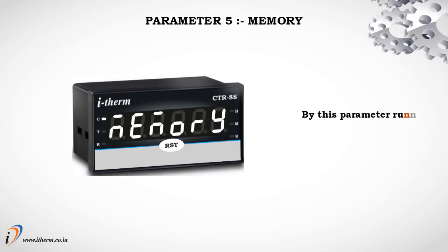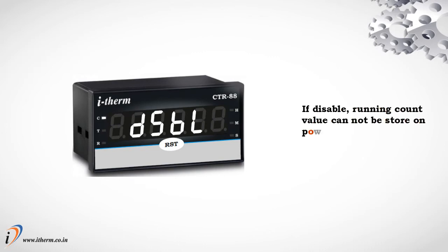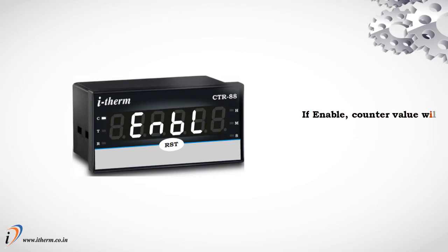Parameter 5: memory. By this parameter, the running count value can be stored on power failure. If disabled, the running count value cannot be stored on power failure and on next power on the counter will be reset. If enabled, the counter value will be stored in memory on power failure.